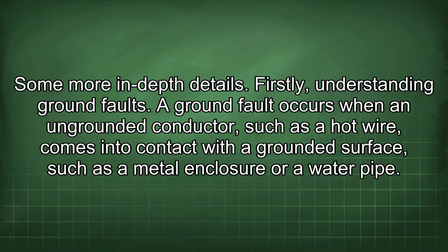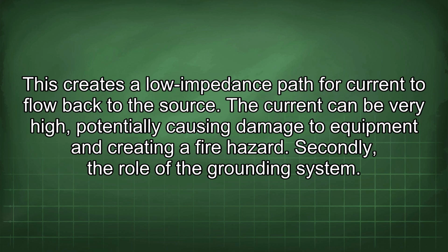Some more in-depth details. Firstly, understanding ground faults. A ground fault occurs when an ungrounded conductor, such as a hot wire, comes into contact with a grounded surface such as a metal enclosure or a water pipe. This creates a low impedance path for current to flow back to the source. The current can be very high, potentially causing damage to equipment and creating a fire hazard.